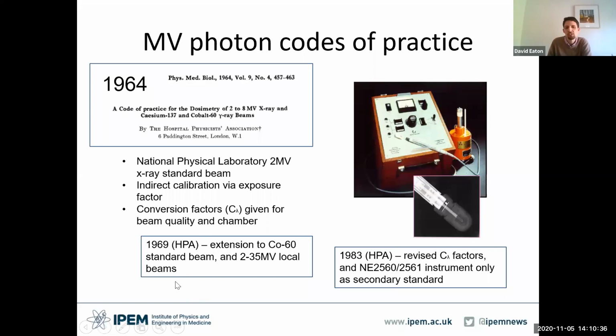Now, there were a couple of extensions to this code. In 1969, it was extended to use the cobalt standard beam and also a much wider range of energies. In those days, I guess it was felt that much higher energies might be useful in clinical practice. I think we've since realized that 35 MV is a bit high really for our purposes in radiotherapy. Maybe even above 15 is unnecessary in many settings. But at this stage, the full range was available, but again, through all these different conversion factors.